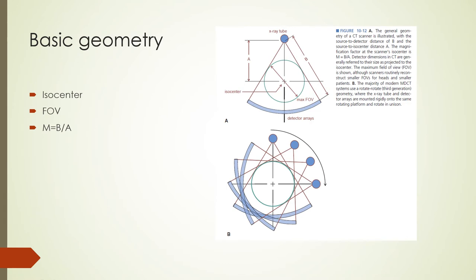The basic geometry of the CT scanner shows the ISO center as the center of rotation. Images are reconstructed at the ISO center on a 512 by 512 matrix. Because of the fan beam geometry, the maximum field of view is defined by the maximum extent of the detectors. As in radiographic imaging, there is a magnification factor from ISO center to the detector location given by M equals B divided by A, which is accounted for in reconstruction.